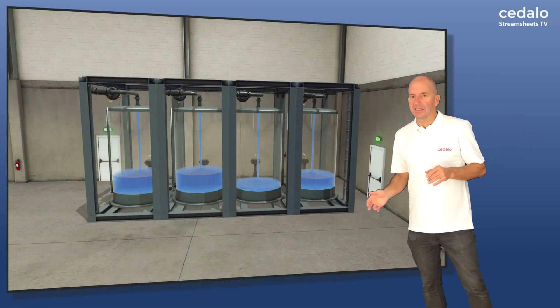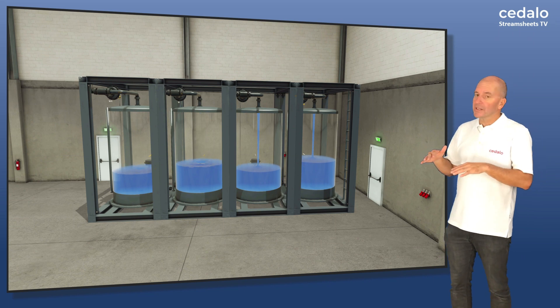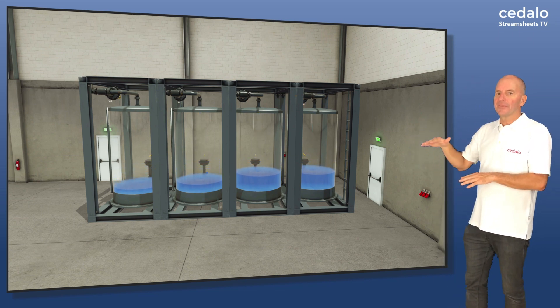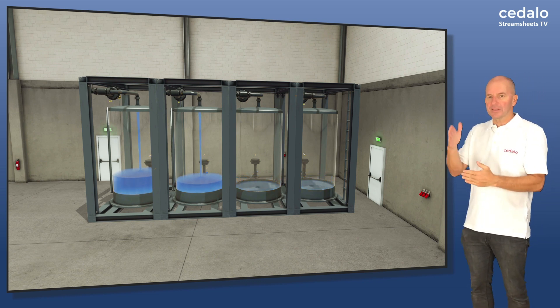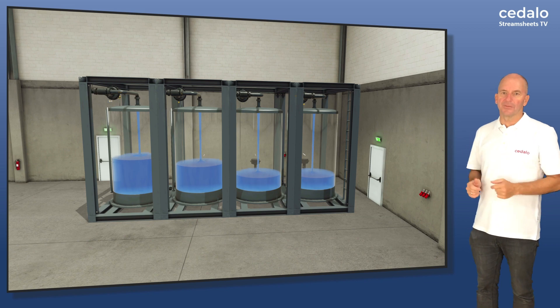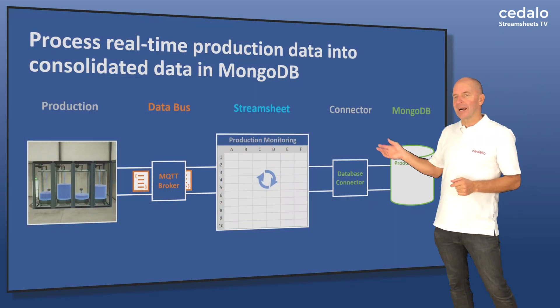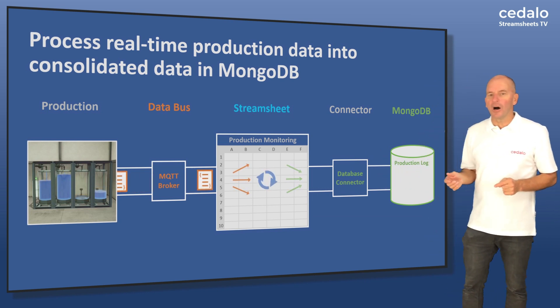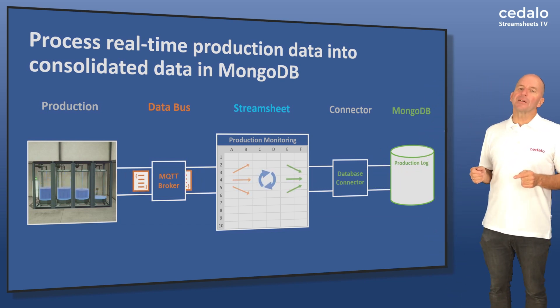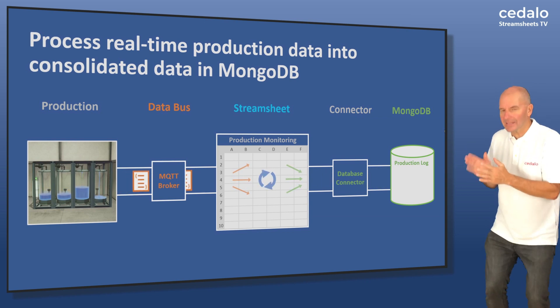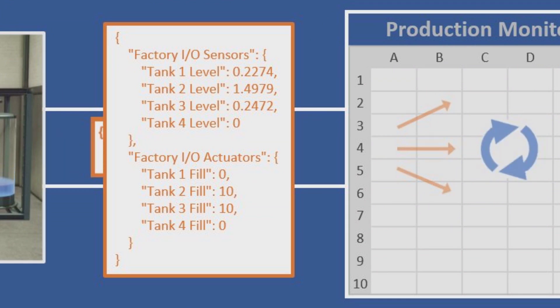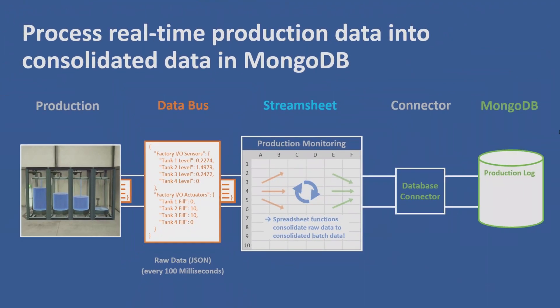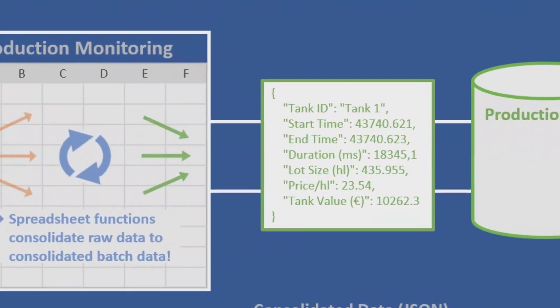Here we see the production facility in detail. Quantities of liquids with varying batch sizes are filled in a repeating production process, and we have sensors that continuously report the level and the status of the inlet valve. The sensors publish their values every hundred milliseconds to a specific topic on the MQTT broker. The StreamSheet recalculates itself at exactly the same frequency. The sensor data is formatted and directly and dynamically linked to the StreamSheet cells.